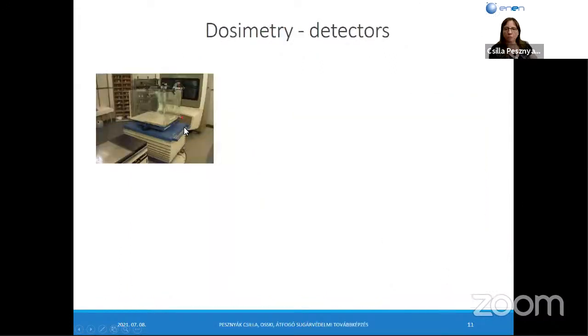Okay, for dosimetry, we use a lot of different equipment, a lot of different phantoms and ionization chambers. And now you can see here the basic element. Without this phantom, we cannot work in radiation therapy centers. It is a water phantom. After that, we use different ionization chambers. Our ionization chambers are quite small. This is the biggest. It is a Farmer type chamber. And when you want to measure in air, you can use this build-up cap to compensate for the build-up region, which I showed before. The Farmer chamber we mostly use for the absolute calibration of the beam.